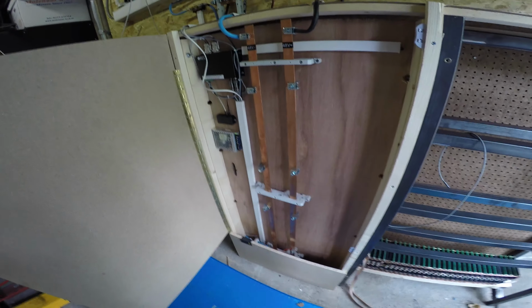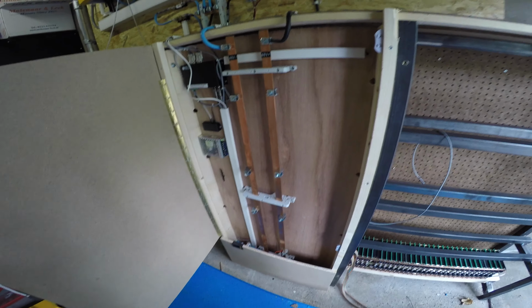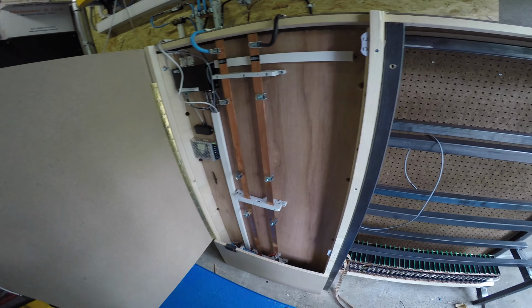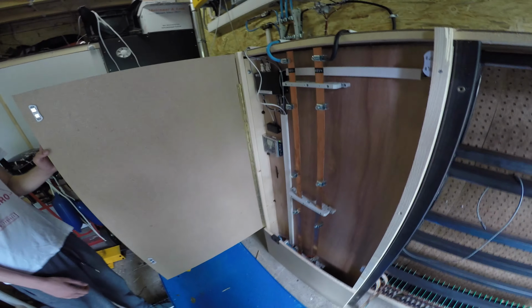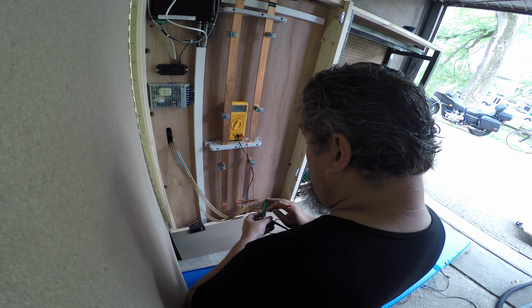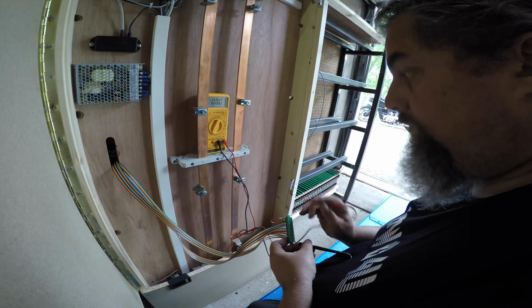As you can see on the bottom, the battery is installed. We're now doing the balancing lead and making sure all the voltages pan out, that the plus and minus is not reversed, because that would fry the BMS for sure.